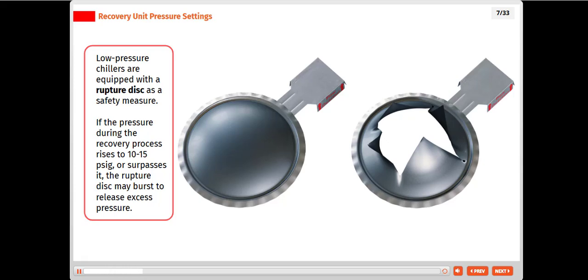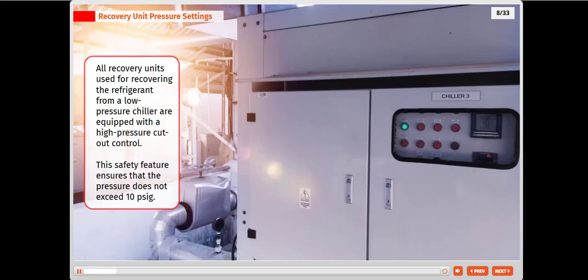Low-pressure chillers are equipped with a rupture disc as a safety measure. If the pressure during the recovery process rises to 10 to 15 psig or surpasses it, the rupture disc may burst to release excess pressure. All recovery units used for recovering the refrigerant from a low-pressure chiller are equipped with a high-pressure cutout control. This safety feature ensures that the pressure does not exceed 10 psig.